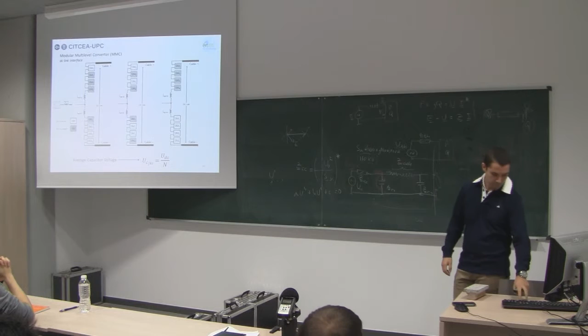Another detail about this converter: in contrast to previous generations, where you had capacitors at the DC side, at the DC bus—here you don't. All the capacitors are inside the submodules. So it's absolutely mandatory that the number of submodules connected sets the DC voltage that is present there.